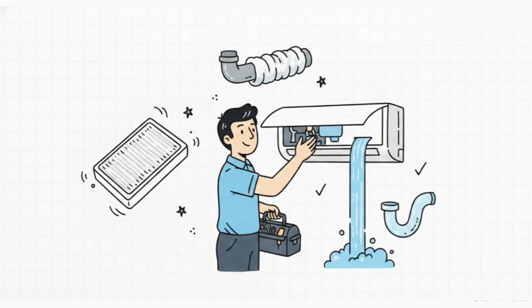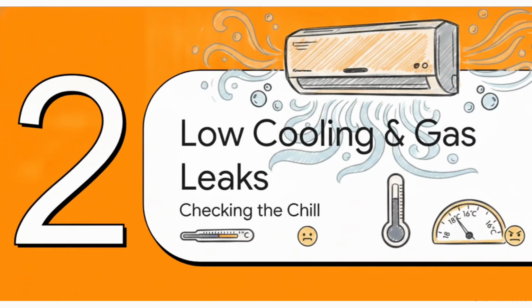But hey, the good news is this is highly preventable. Here's a crucial pro tip for you. Get a full professional service every 2 to 3 years. Regular servicing ensures those copper pipes stay properly wrapped and insulated, the filters are kept clear of deep dust, and the drain pipes are fully flushed out. This essentially stops these watery messes before they even have a chance to start. Moving right along to Section 2, low cooling and gas leaks.